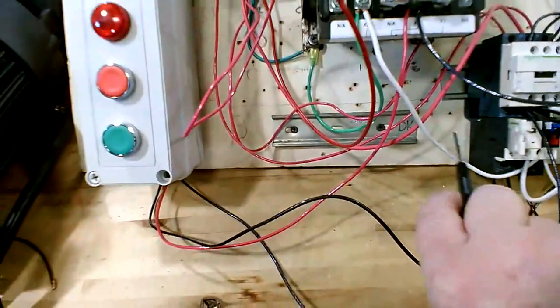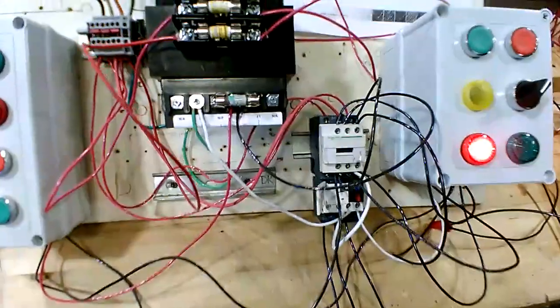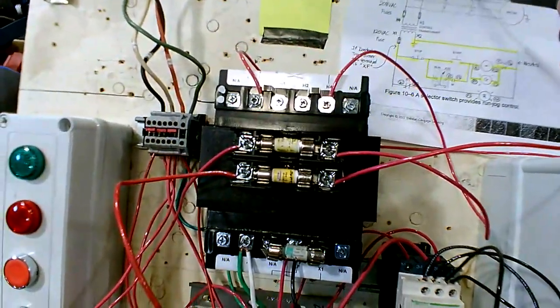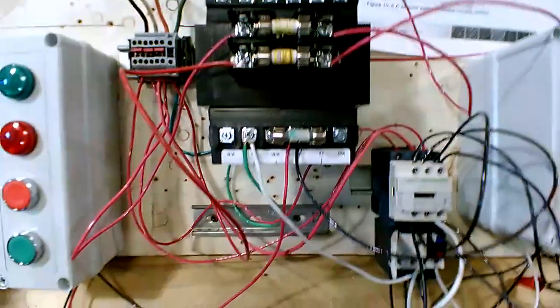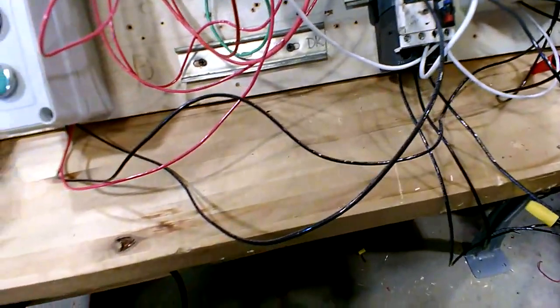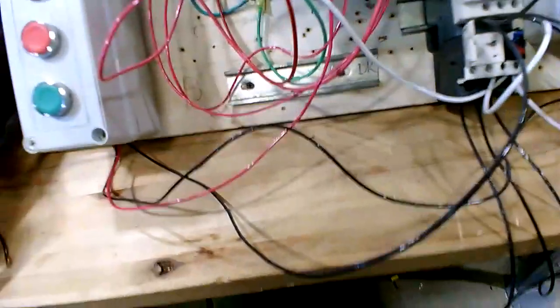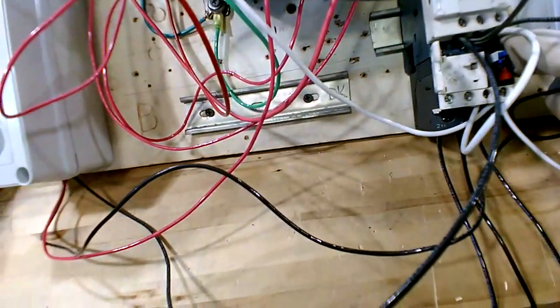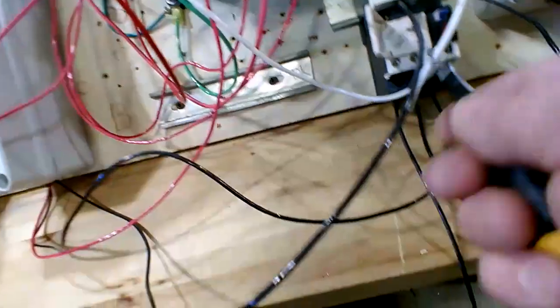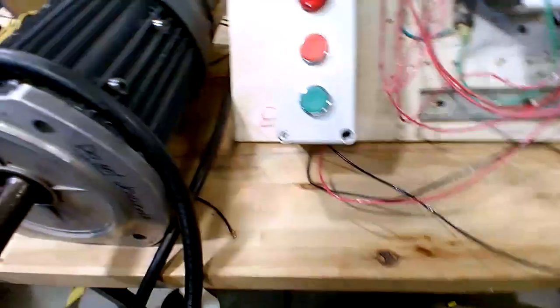It's an overload relay. Like if the motor stalls and binds up or something jams on the chain, the overload heaters get hot, and where it says OL, it'll make that trip. It just loses the neutral leg, the coil just disengages. You can reset it by hitting the blue button. Close this up. Just hit the blue button with it open. It's quick, and it cleared the fault, now it'll go ahead and run.